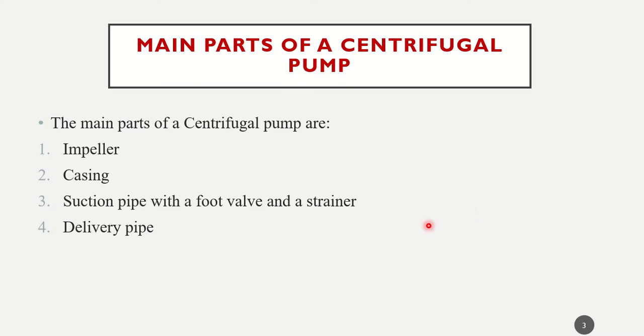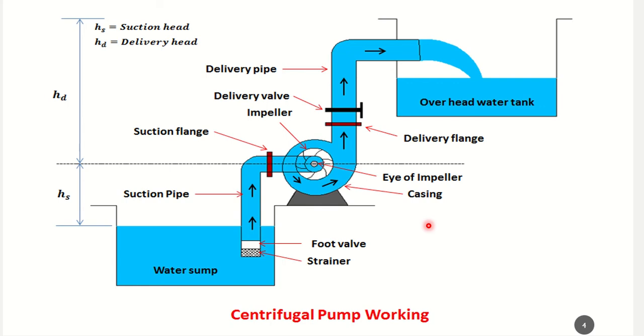Coming to the parts of a centrifugal pump, there are four important components. First is the impeller — the rotating part of the pump. The rotating part of a turbine is called a runner, while the rotating part of a centrifugal pump is called an impeller. This impeller has vanes or buckets fitted inside. Next is the casing — a protective cover all around the impeller. Then you have a suction pipe with a foot valve and strainer, and a delivery pipe.